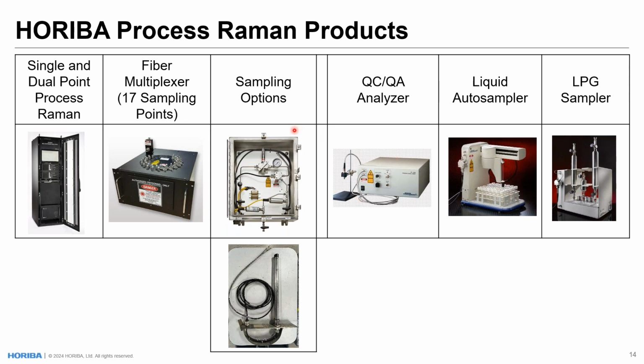Likewise, with our sampling options here, this is a picture of that process flow cell that helps with inline process analysis without disturbing flow or perturbing the sample stream, etc., if that is a worry or concern. Down here is an image of a typical immersion probe that allows for direct insertion into the process line.